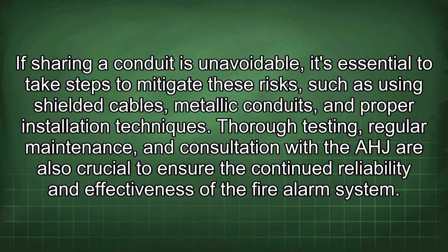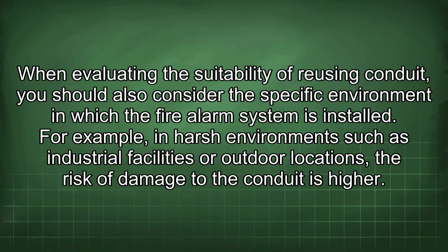If reusing a conduit is unavoidable, it's essential to take steps to mitigate these risks, such as using shielded cables, metallic conduits, and proper installation techniques. Thorough testing, regular maintenance, and consultation with the AHJ are also crucial to ensure the continued reliability and effectiveness of the fire alarm system. When evaluating the suitability of reusing conduit, you should also consider the specific environment in which the fire alarm system is installed.